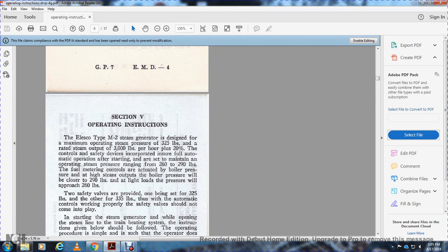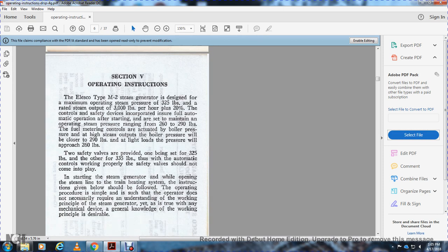Fuel metering controls are actuated by boiler pressure. At high steam output, the boiler pressure will reduce to 290 pounds. At light loads, the pressure will approach 260 pounds. Two safety valves are provided, one set at 325 pounds, the other at 335 pounds. Thus, with the automatic controls working properly, the safety valves should not come into play.